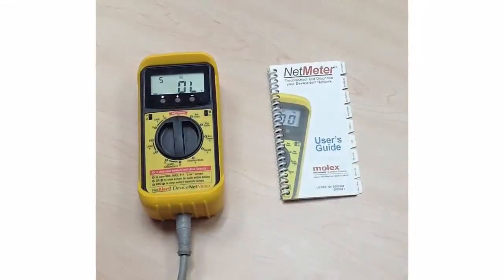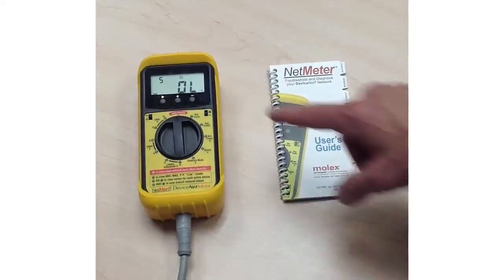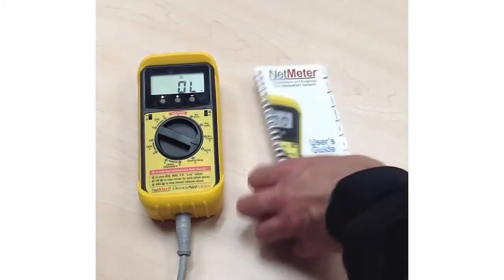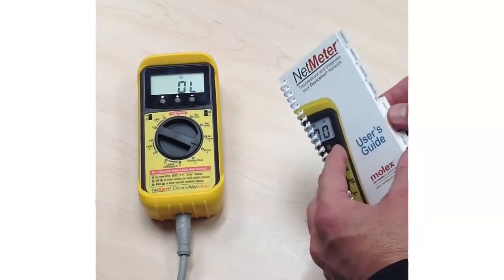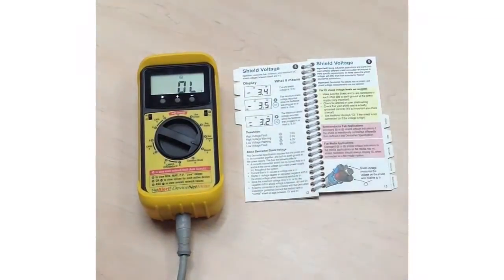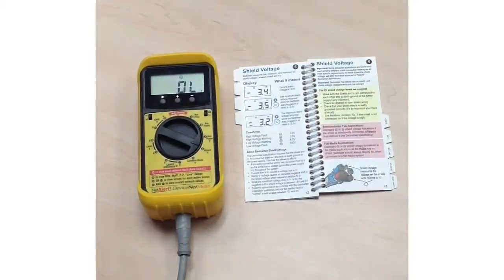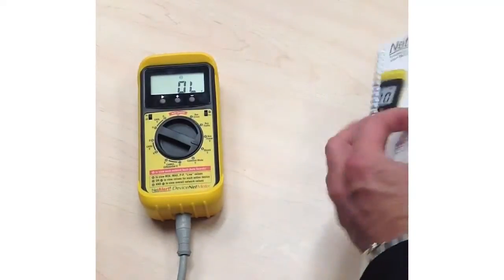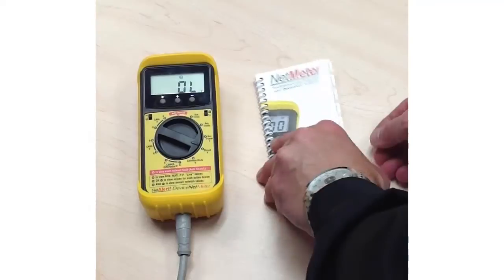In this case, we're looking at an out-of-limit reading for the shield — that's reading number five. The user rotates to position number five on the dial, and also opens up the user's guide to check the information pertaining to shield voltage. There's a great explanation of what shield voltage is and what it's measuring, and this section explains what a shield voltage problem indicates and how to fix it. For every parameter measured by the DeviceNet NetMeter, there's a corresponding position on the rotary dial and a corresponding tab in the user's guide.